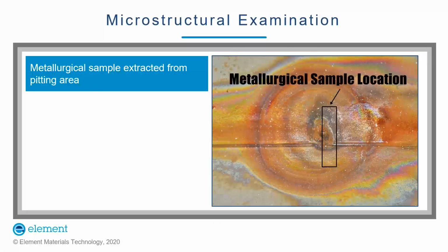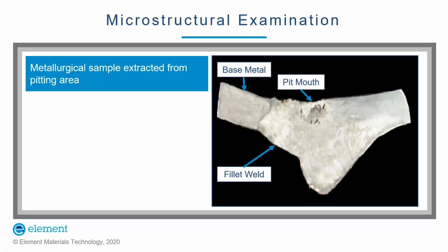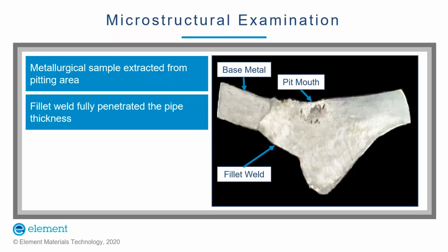During visual examination, the leakage points were found, and in order to observe the cross-section of the leak locations, a metallurgical sample was cut from the pit for metallurgical assessment. Polishing and etching of the sample was carried out to differentiate between weld and base metal. The macro photograph shows cross-sectional views of the metallurgical sample, which revealed pitting in the weld. It was observed that the fillet weld, which was used to weld the support plate to the pipe, fully penetrated the pipe thickness. No welding defects were found in the weld, like lack of fusion or cracking.